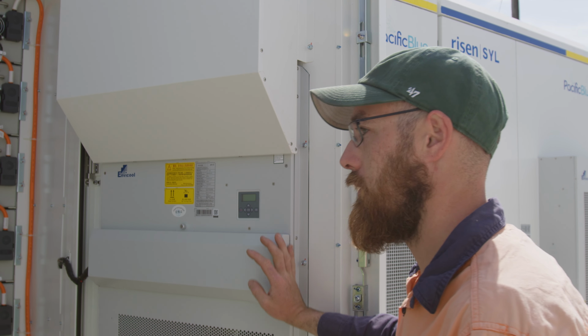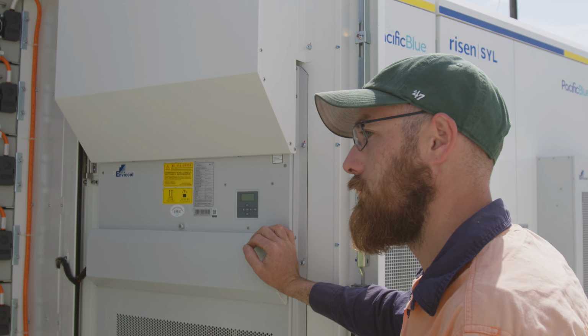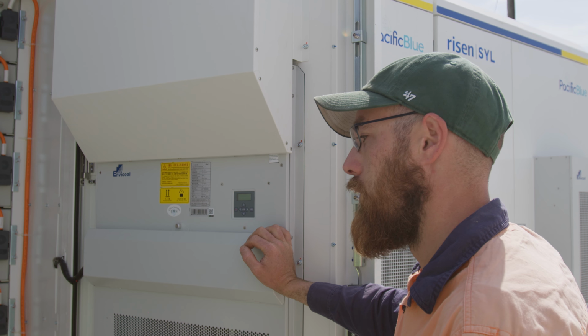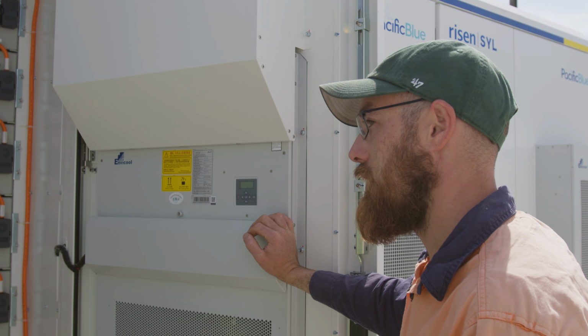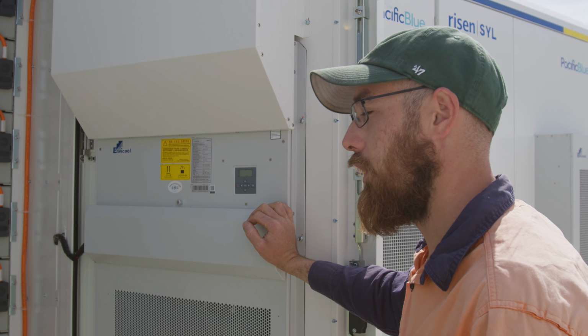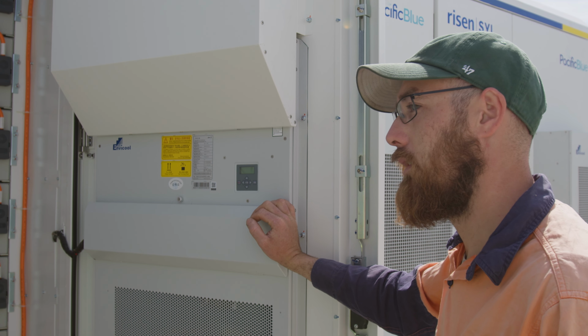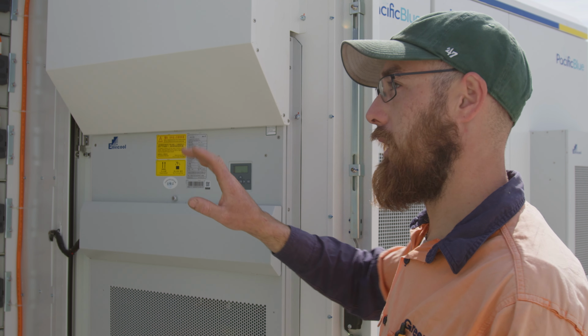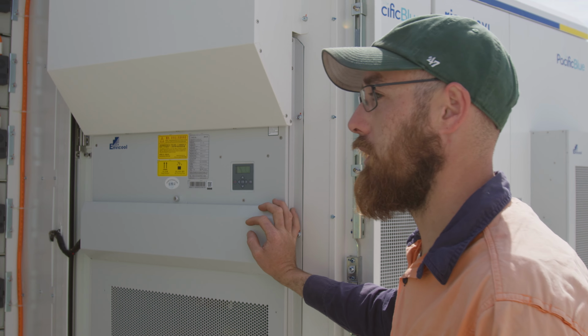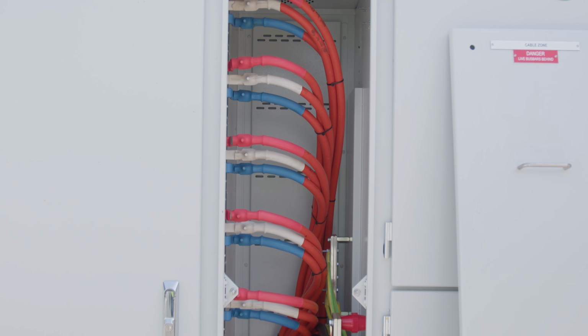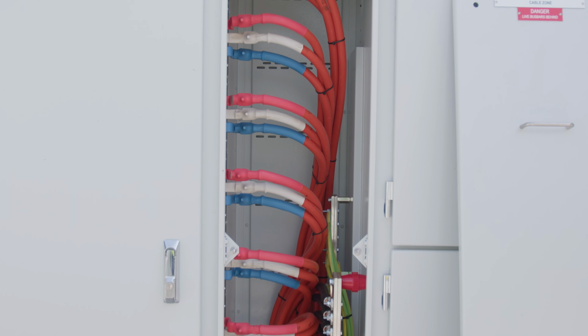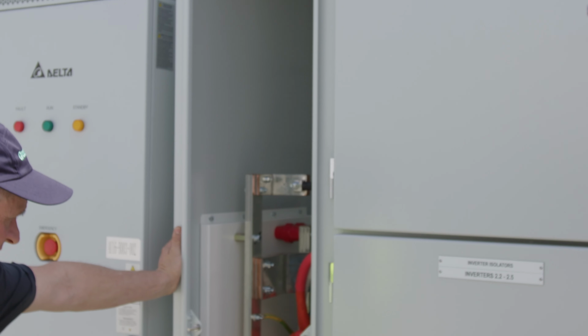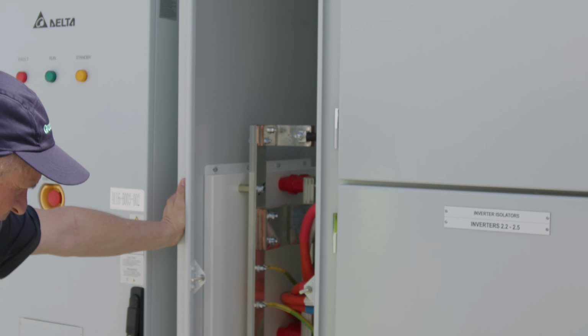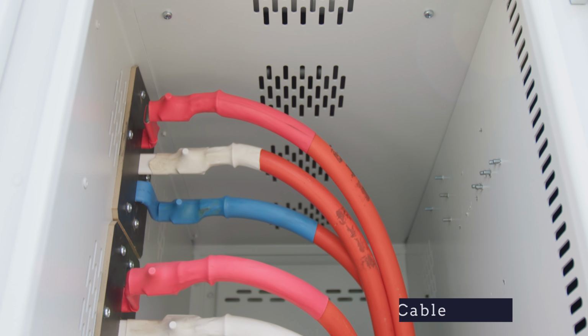And who has authority, or who will have authority, to change those settings? That won't be able to be changed by the distributor. That will only be able to be changed by the system owner. They will have access to change that either on site or remotely via the site manager. Okay, I noticed this is the MEN link here. Can you just run us through the cabling? What have we got? What's the cable capacity here?